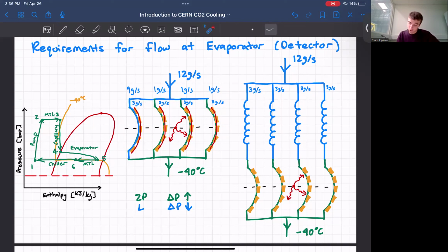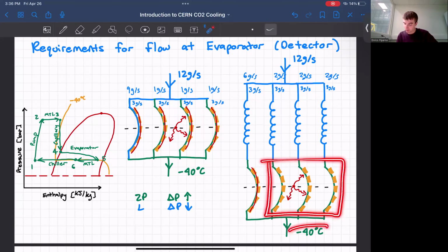However, if we introduce capillaries, we're increasing the total pressure drop along the evaporator. As a result, the failure of one evaporator would no longer be as dramatic. So now say that this evaporator breaks. The flow will still increase in this loop, but not as dramatically. As a result, these silicon sensors will still be able to cool to minus 40 degrees Celsius.